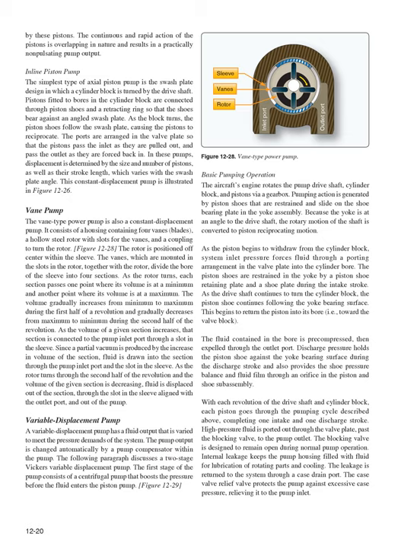In Figure 12.28, the rotor is positioned off-center within the sleeve. The vanes, which are mounted in the slots in the rotor, together with the rotor, divide the bore of the sleeve into 4 sections. As the rotor turns, each section passes one point where its volume is at a minimum and another point where its volume is at a maximum. The volume gradually increases from minimum to maximum during the first half of a revolution and gradually decreases from maximum to minimum during the second half of the revolution.